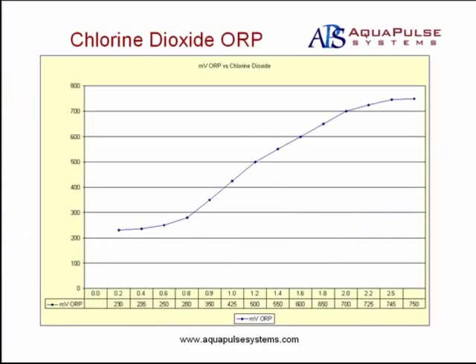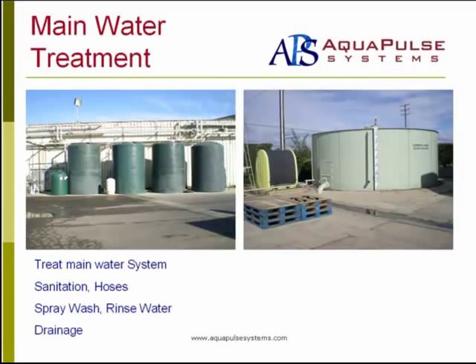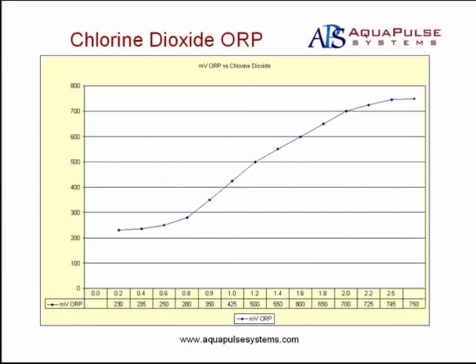There's a correlation between oxidation reduction potential and dose rate for chlorine dioxide. As you can see from this chart, precise dosing is achievable using ORP control for most water systems.